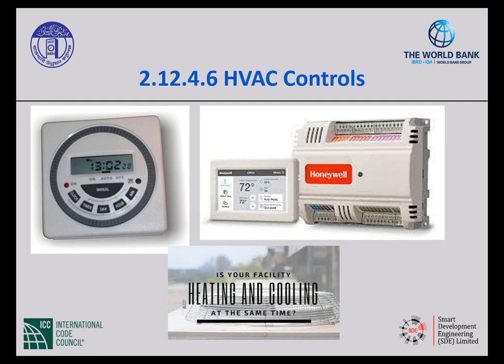All heating and cooling system equipment shall be temperature controlled. Where a unit provides both heating and cooling, controls have to be capable of providing a 5-degree Fahrenheit, 3 degrees Celsius, deadband. So this keeps us from simultaneously heating and cooling throughout the day. So what is that talking about? If I'm in a building and in the wintertime I'm heating it, there is a very good chance that I'm also air conditioning my building, because at certain points the amount of people, the amount of sunshine coming in the window, or the amount of equipment in that building are all putting off heat. Eventually, even in the wintertime, I am likely running air conditioning to provide either some of my ventilation, or to deal with humidity in the air, or just to deal with the heat that's being put off. I'm running my air conditioner.